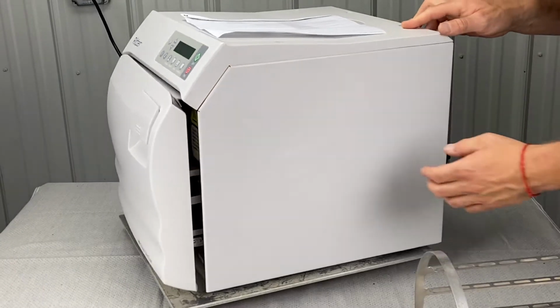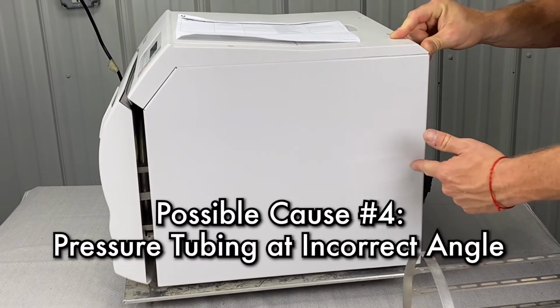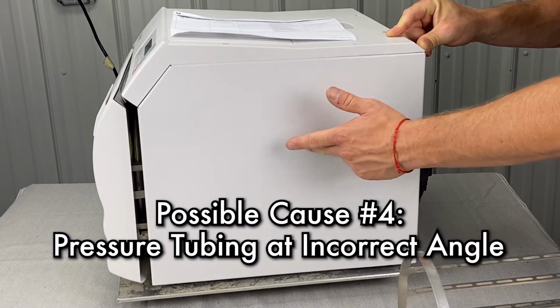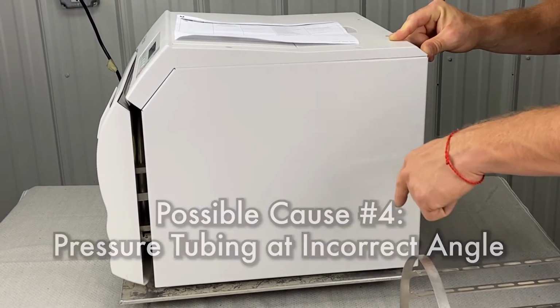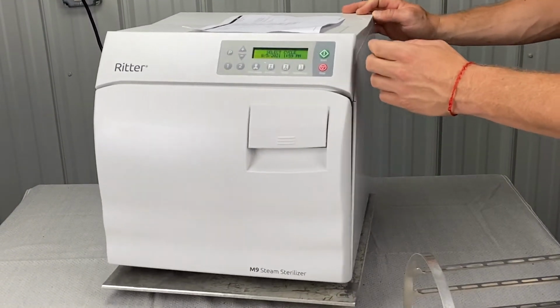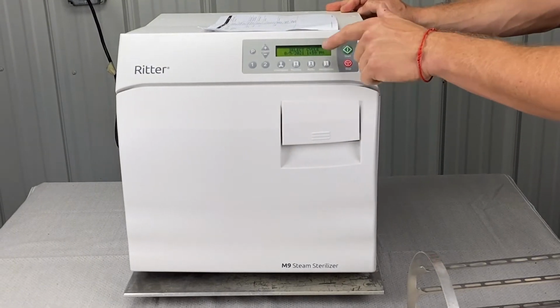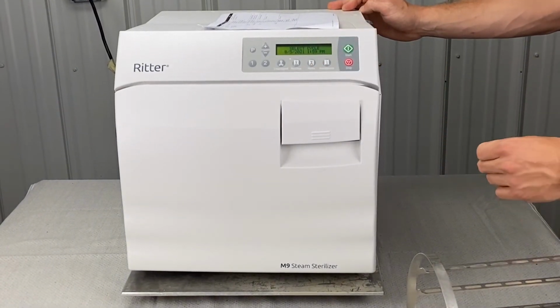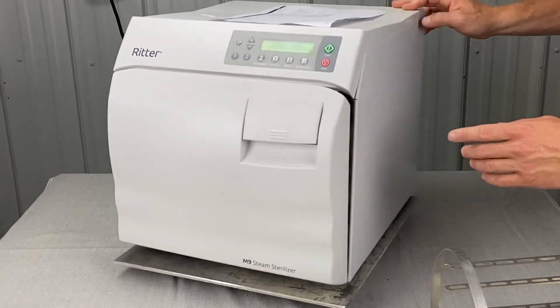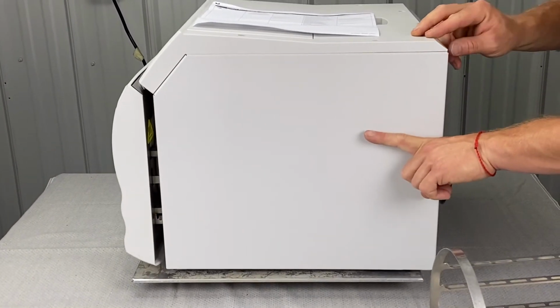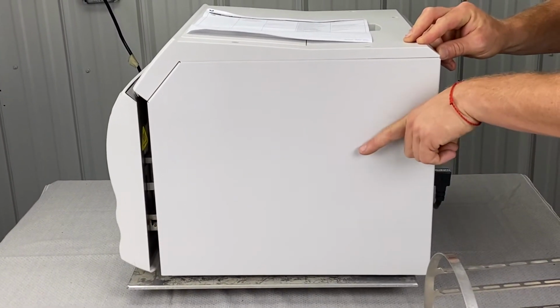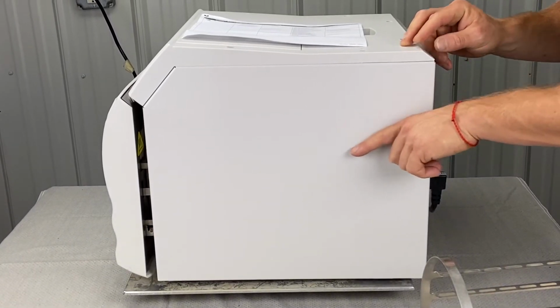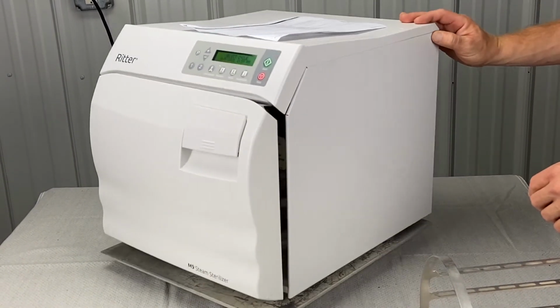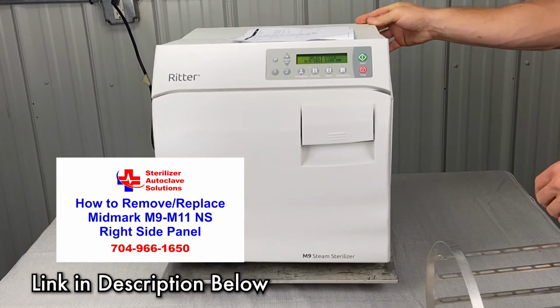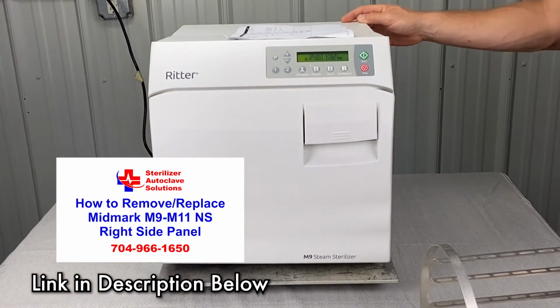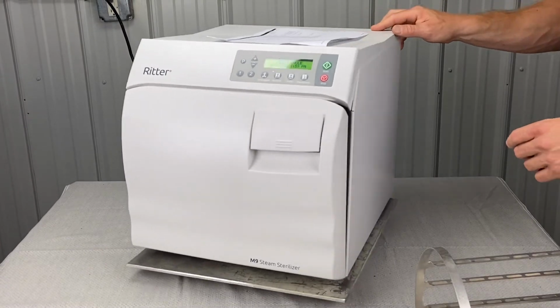Also, you can't see here, but there is a pressure tubing that comes from the pressure transducer. It goes into a piece of plumbing, and basically it turns the pressure inside of the chamber into an electrical signal, so the computer can read it and function. They should be positioned in a downward trajectory. If they're upward like this, it can cause the sensor itself to flood. Again, refer to other videos on how to take that panel off, and you'll see what I'm talking about, or call our tech support line. We'd love to walk you through it.